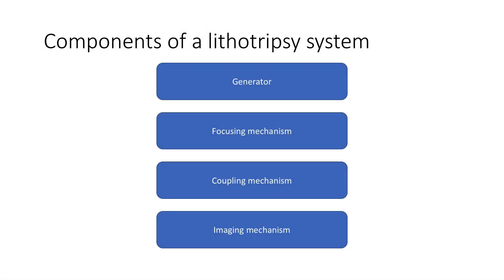First, let's think about the essential components of any lithotripsy system, regardless of the type of lithotripsy. You need a shockwave generator, you need some means of focusing the shockwaves onto the stone, you need a coupling mechanism — that is a way of transmitting the shockwave from the generator into the patient's body — and finally you need a reliable form of imaging, either fluoroscopy or ultrasound or indeed both, which will allow you to localise the stone for treatment.